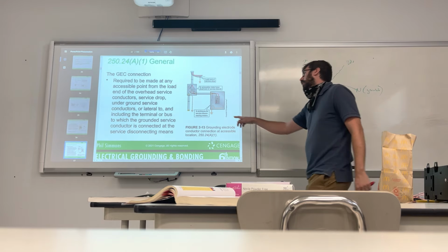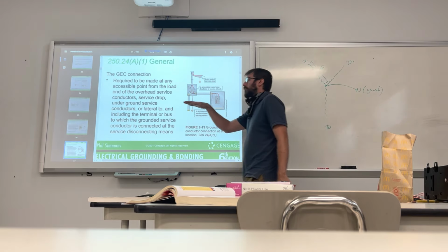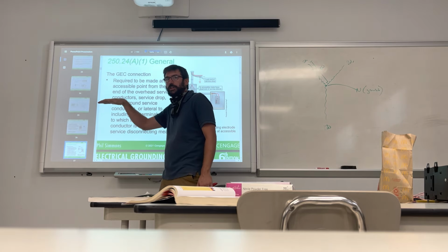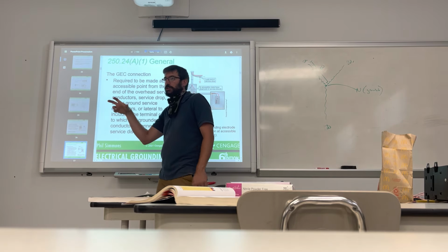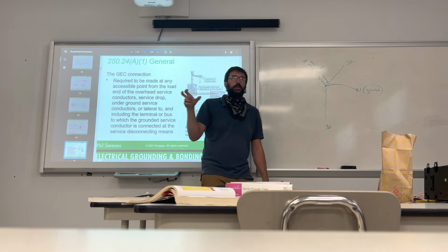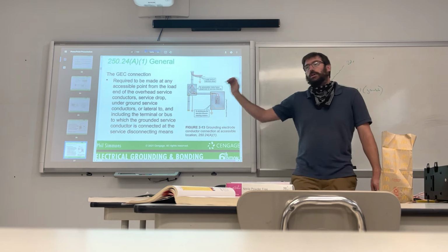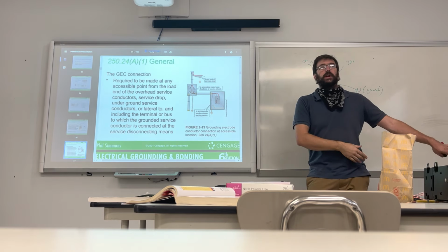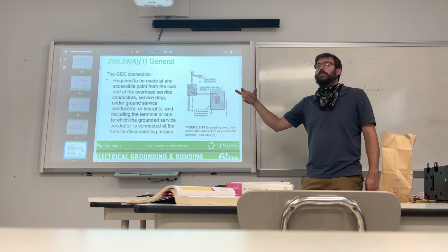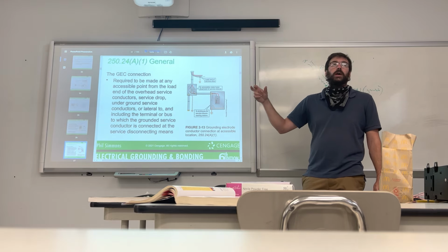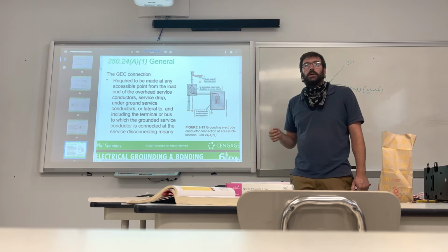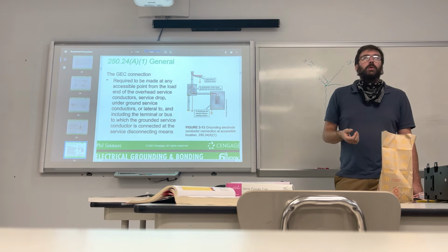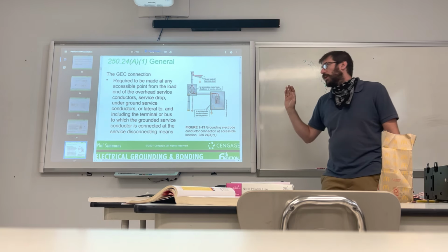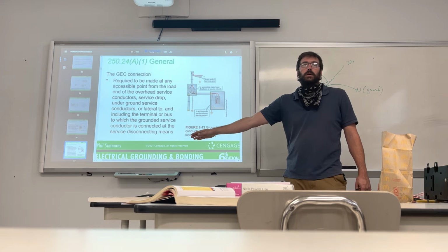When that wire comes out of your main panel box, on its way to the ground rods, it stops just outside of your house, and there's a little terminal right there. It's called a grounding bridge. The ground just passes through that and goes to the ground rods as if nothing ever happened. But that grounding bridge is now an accessible point that guys from Comcast, guys from the water company, when they come to install their meters, they can ground their meters right on that terminal bar.